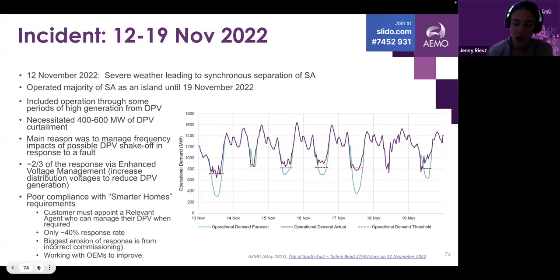The main security risk we were worried about here was while we were operating an island, there is the potential for a fault in the middle of Adelaide that would cause a trip of a unit plus a very large amount of PV disconnecting. And we didn't have adequate frequency reserves to be able to manage that in that island condition and maintain our frequency standards. So the only option we had available to us was to curtail down the PV. So it's harking back to the previous issue. If you can solve the disturbance ride-through issues in the standards, then this issue would be much diminished.